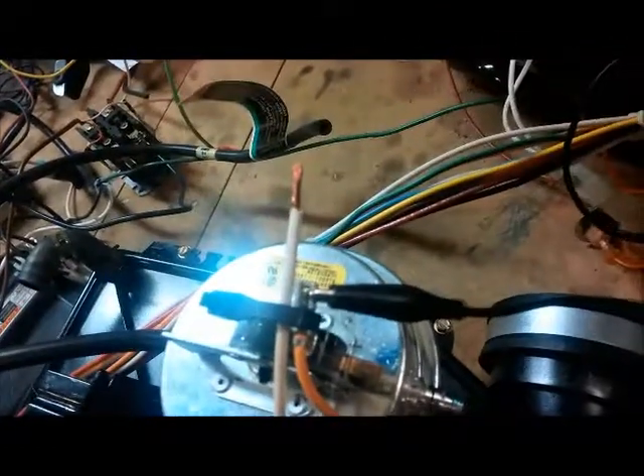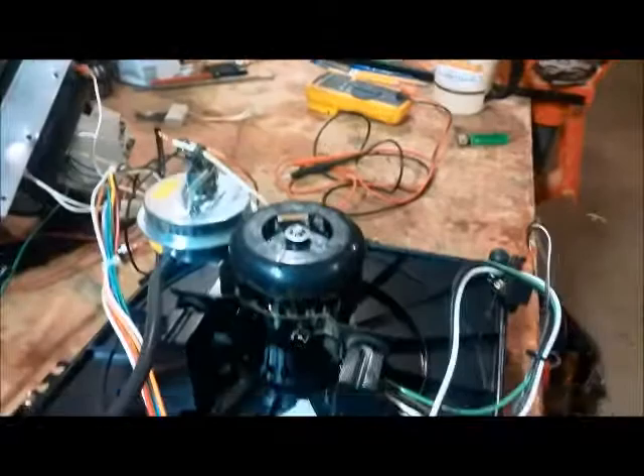Let's take off our call for heat. Open our pressure switch. Now the terms open and closed in heating mean open means disconnected, closed means connected. Closed because those two wires are connected by way of this jumper. Open meaning disconnected. So that's your basic heating circuit.